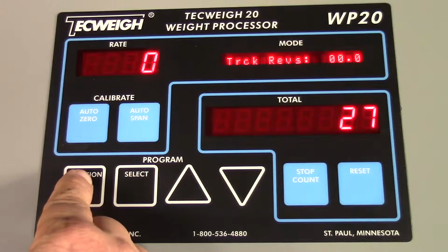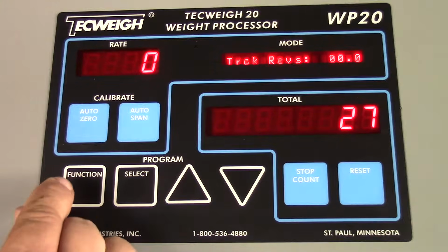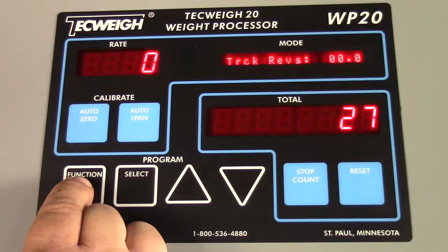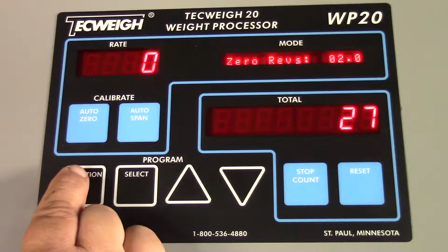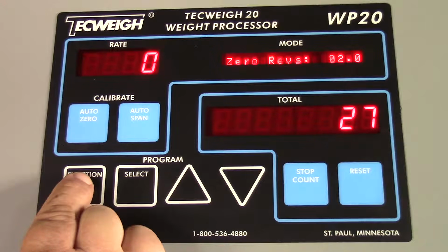Tracking revolutions. Normally we just keep that at 0. 0 revolutions, we could change that to 2 or 3. For most applications, the factory default of 2 is okay. That's the complete revolution of the belt during a calibration. Span revolutions is when we put the test weights on there. That'll tell us how many belt revolutions we want to use for the span calibration.